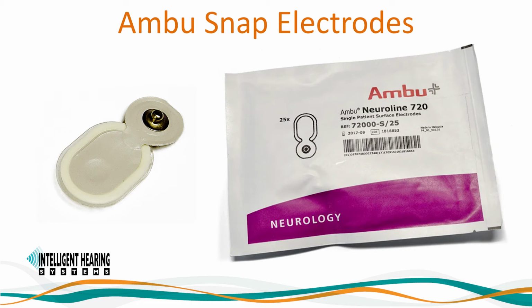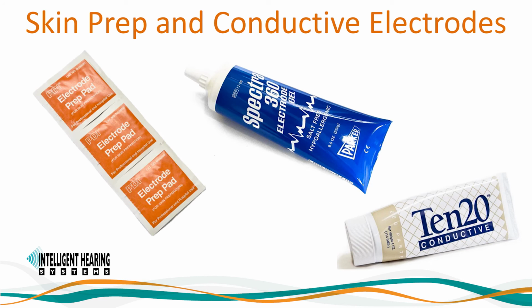Make sure that when placing on these electrodes that you press down on the white outer rim to adhere the snap electrode to the skin. Do not press in the center on the conductive sensor, as the gel may spread and compromise the adhesiveness of your electrode. Electrodes that lift up or slide off during testing will pick up more noise and affect the quality of your recordings. Use skin prep pads to prepare the skin and SpectraGel or Ten20 conductive paste as necessary to enhance impedances.